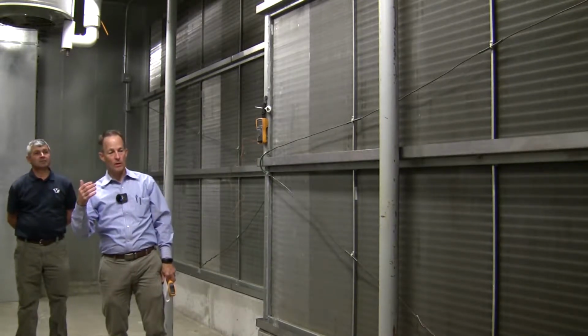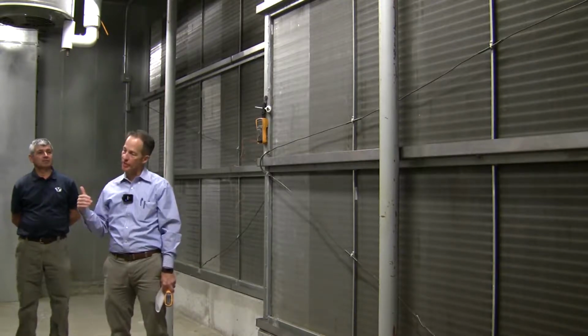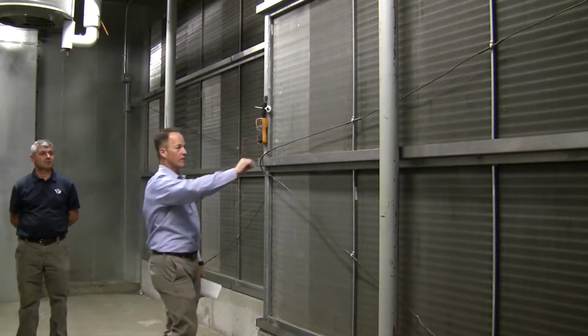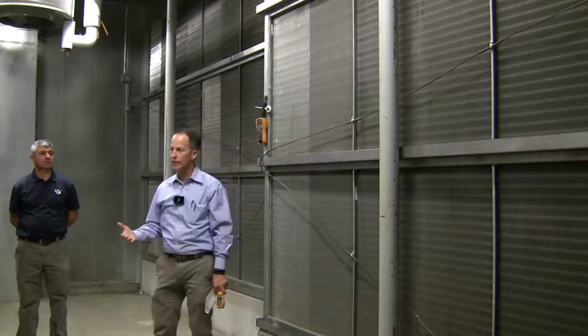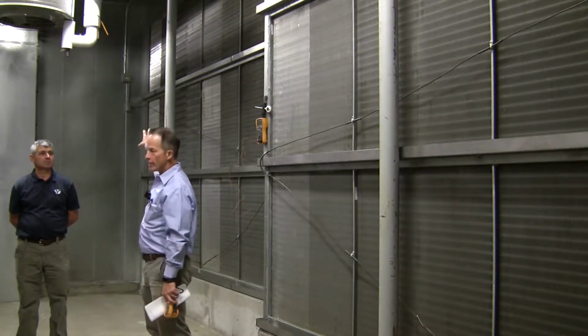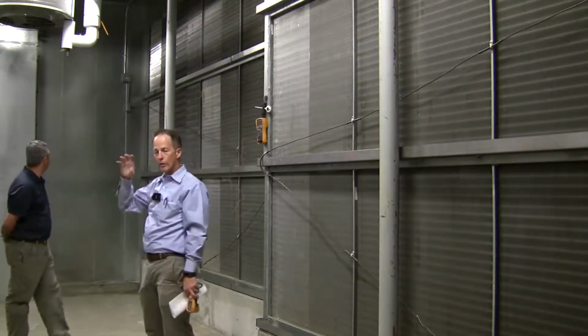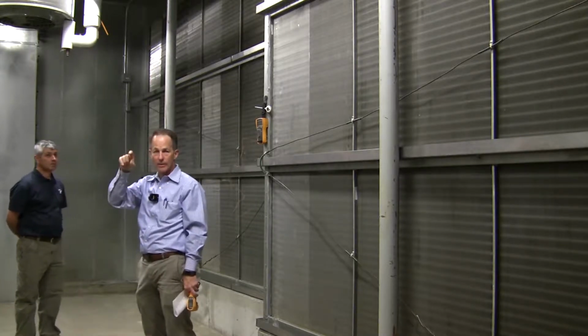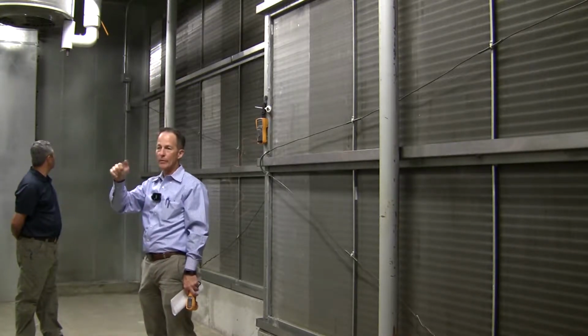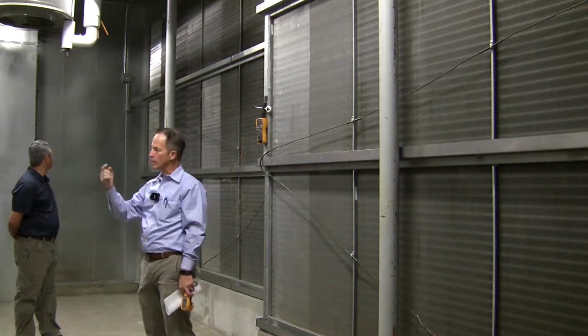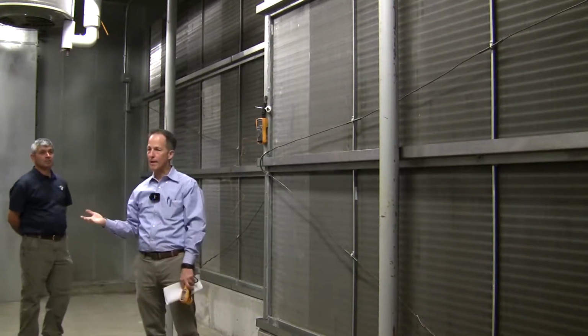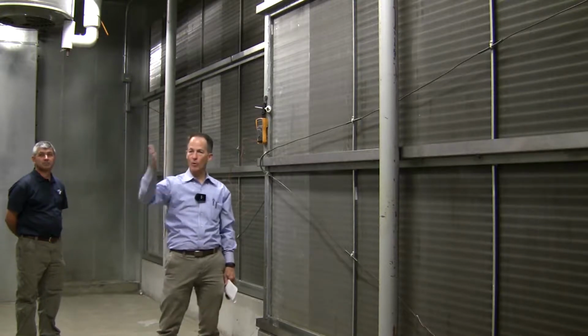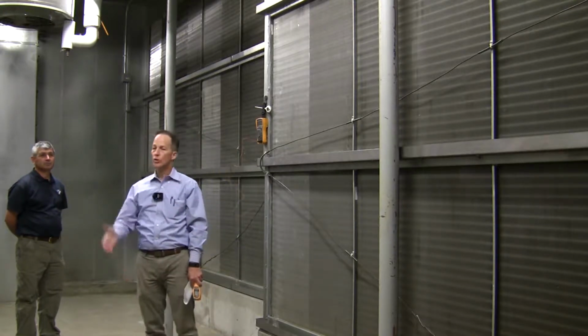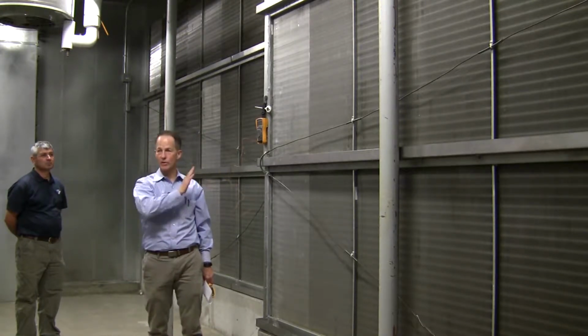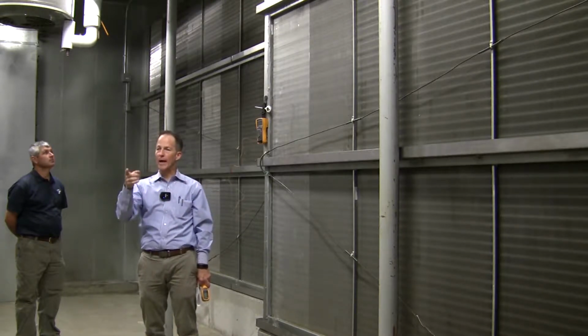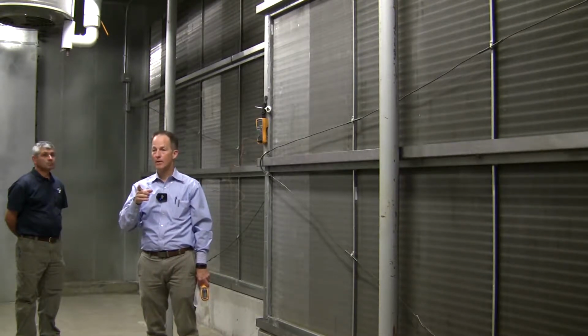So we do have averaging sensors that occasionally have this capillary tube look to it, just like a freeze stat. The one that's over here on the wall, you can look at it, and the way you can tell is, for one, it has a little label on the top, but it also doesn't have a reset button. We'll look at the freeze stats, which are, where should a freeze stat be? On the upstream or the downstream side? So it's actually the downstream, because we want the coil to have a chance to do its job, right?